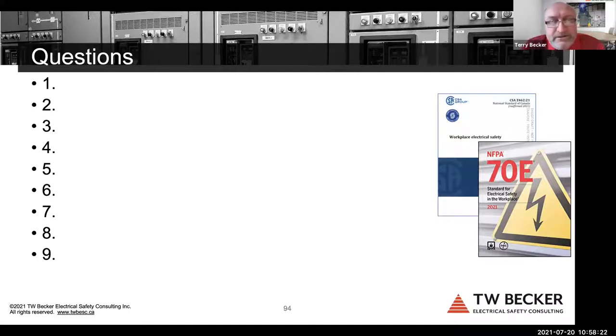So it's not capacity. The arc flash label requirement is an outcome of the IEEE 1584 incident energy analysis, right? So then you can either put that arc flash hazard information, and on the right-hand side, put the shock approach boundaries from 70E and Z462 on the label. That's pretty typical, that label format for the last 14 years I've been doing this. So again, it's doing the calculations, right? And then how do you provide that information to the qualified person? On the labels, typically what industry's done, but as I said, you got to manage the label specification and the information that's communicated on that label.